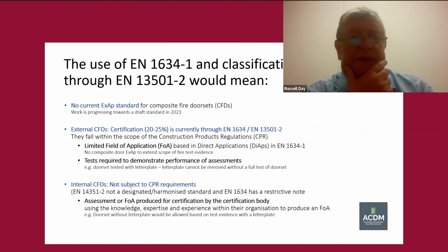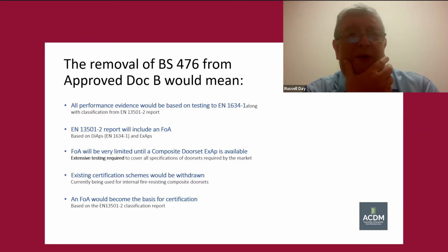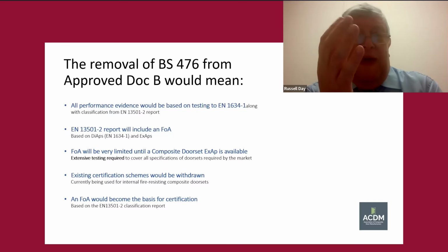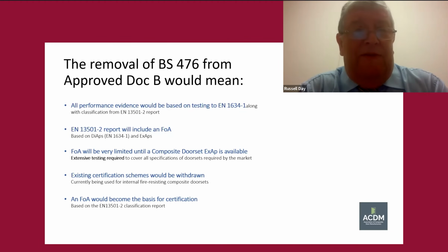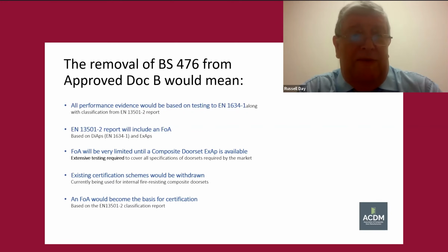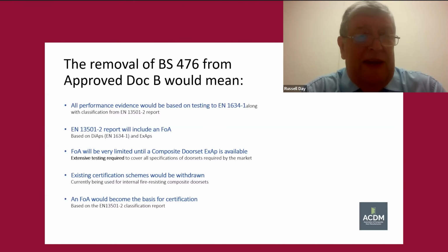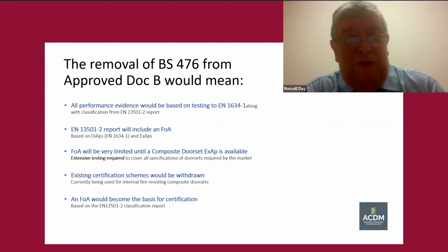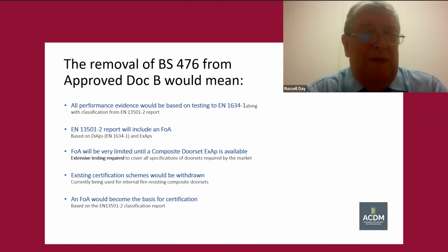So if we look at the next slide, all performance evidence would be based on the 13501 Part 2 test report. That includes a field of application, as I've said, based on DiAps and ExAps. The problem with that is that once that report is issued, any national field of application based on 476 testing would be invalid. They would be withdrawn.